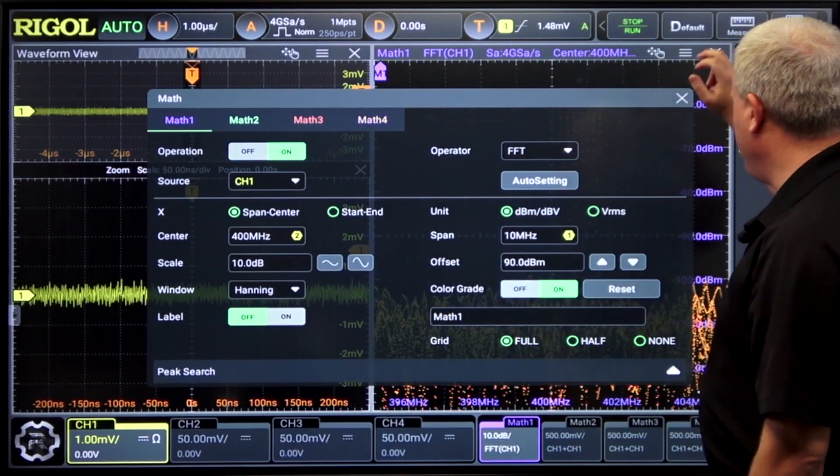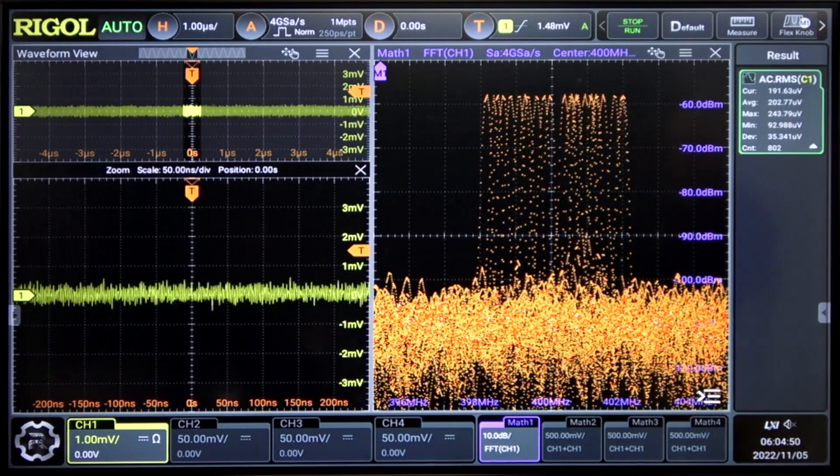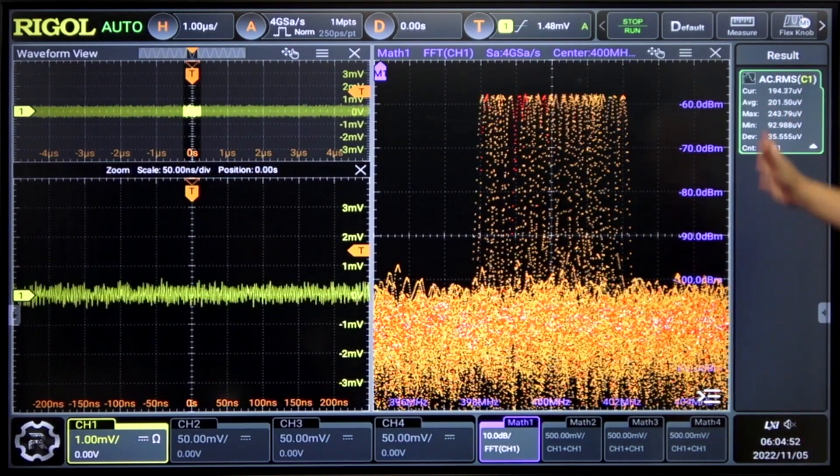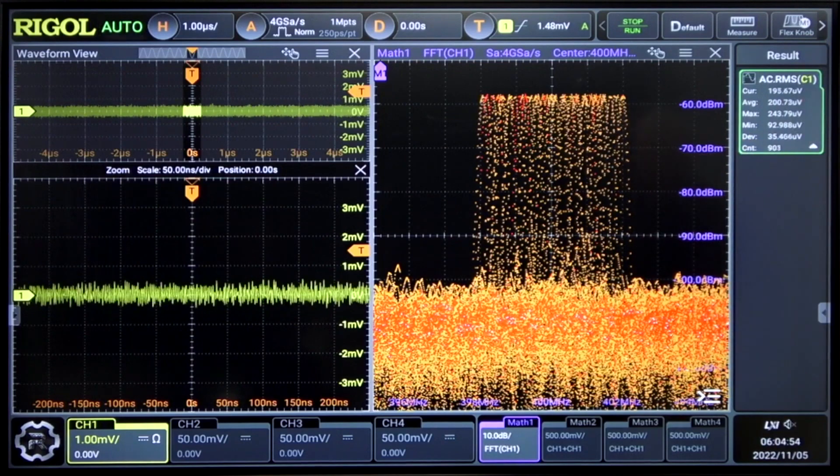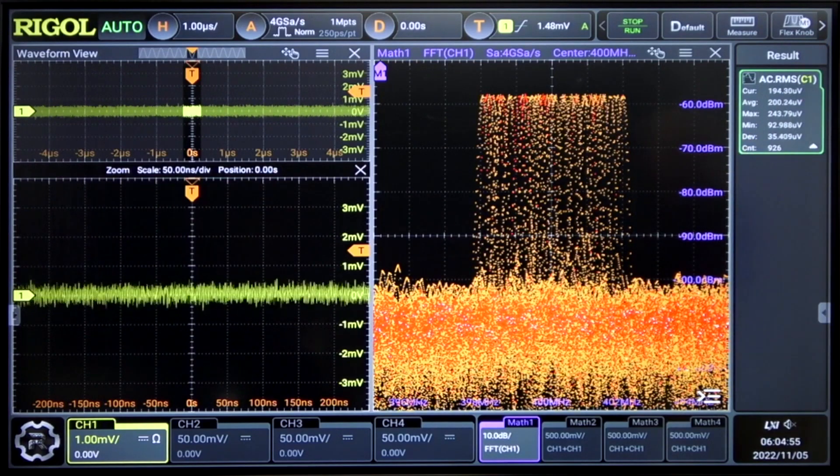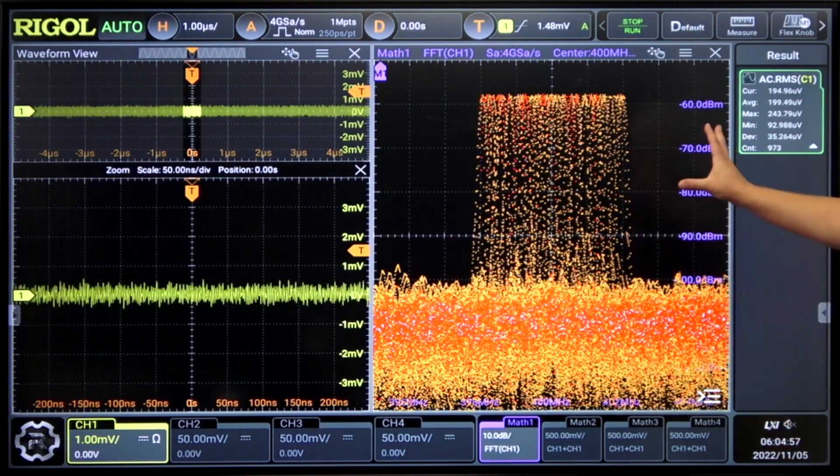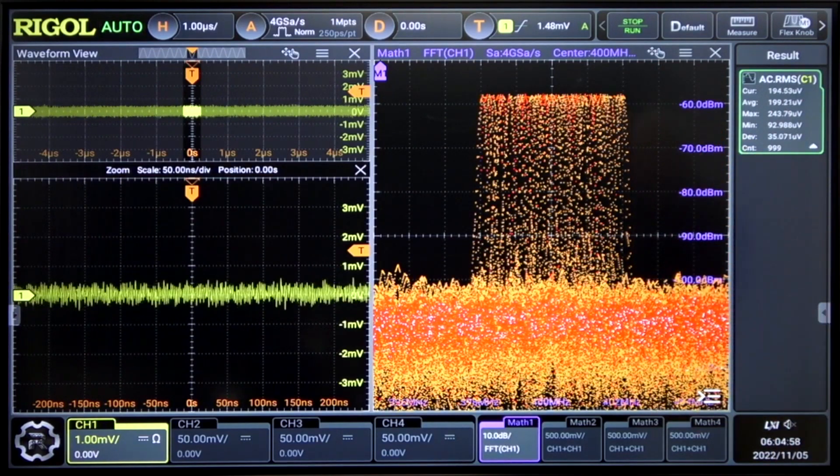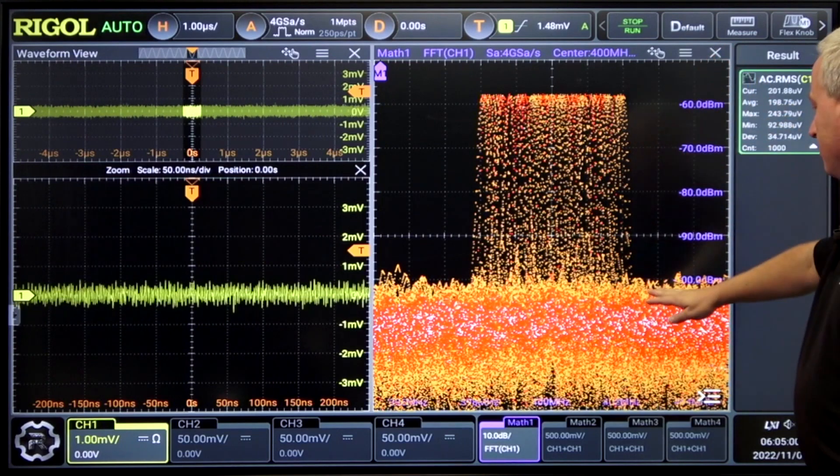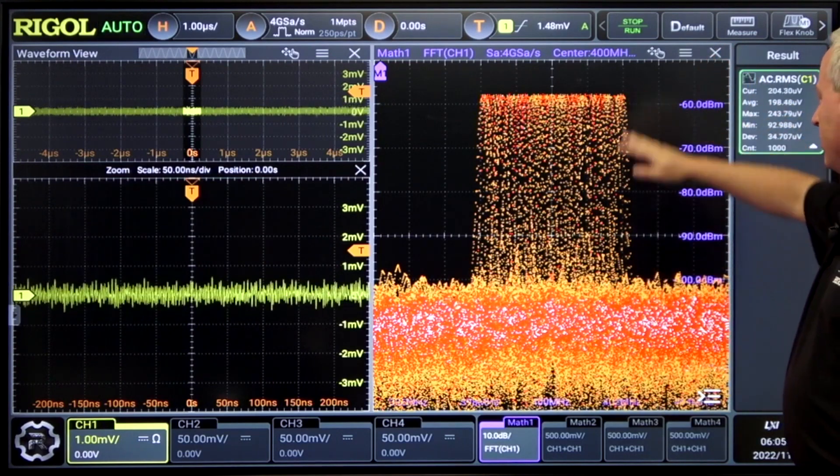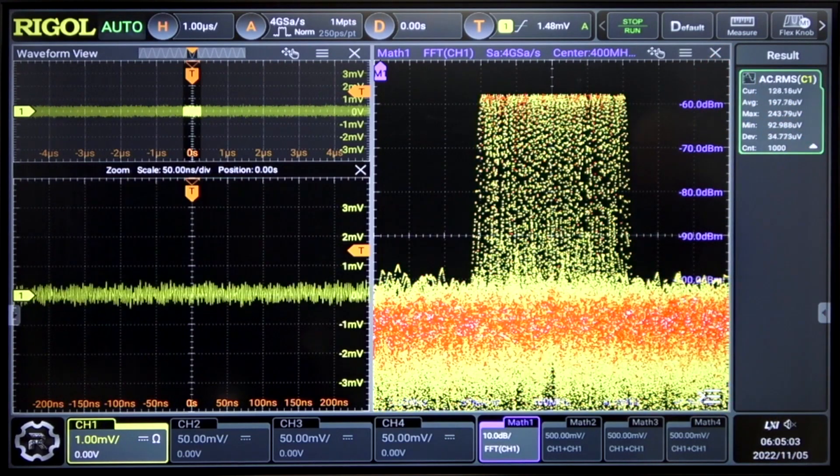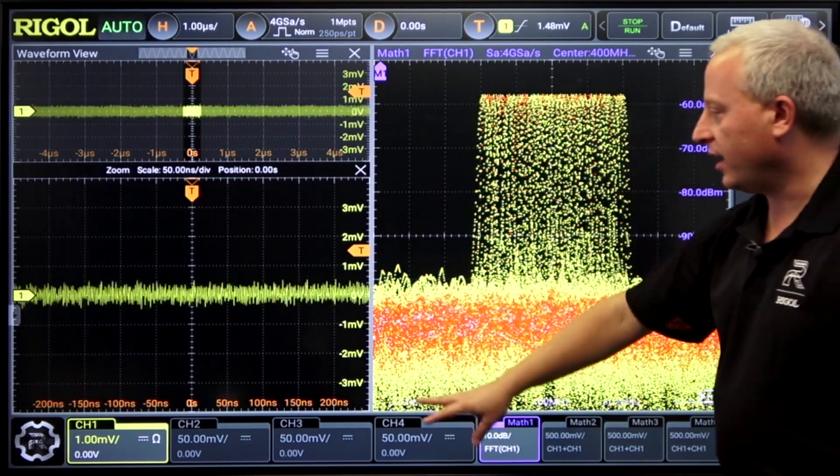And actually this signal is sweeping a little bit. Let's take a look at it with a color grade. So here you can see the flatness of that signal up at 400 MHz. Look at it over time with a color graded display, and get great detail both on signal and noise level on a one millivolt range.